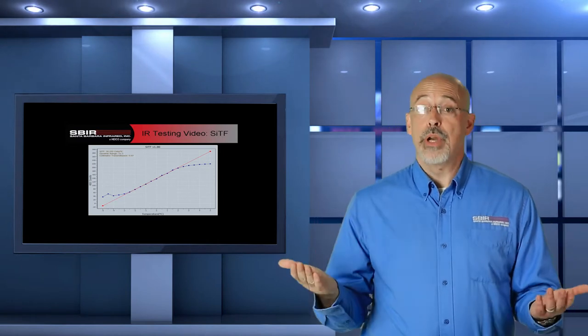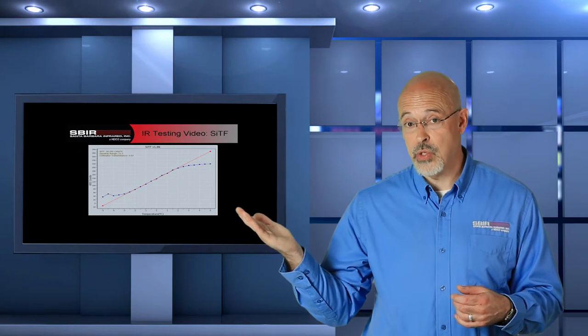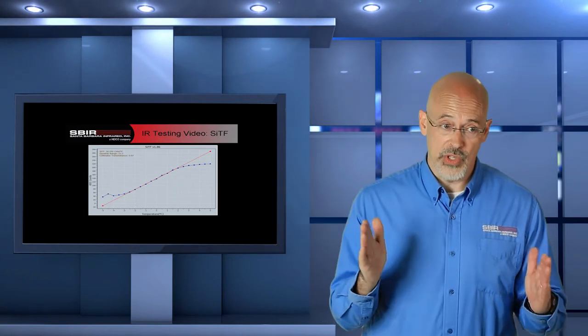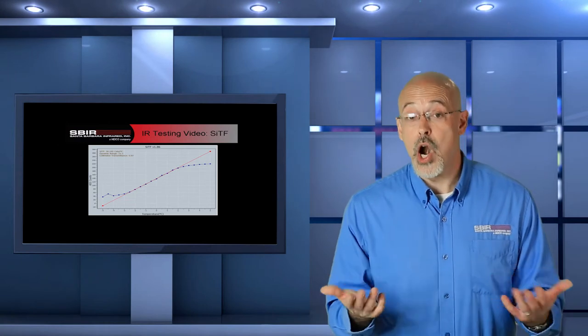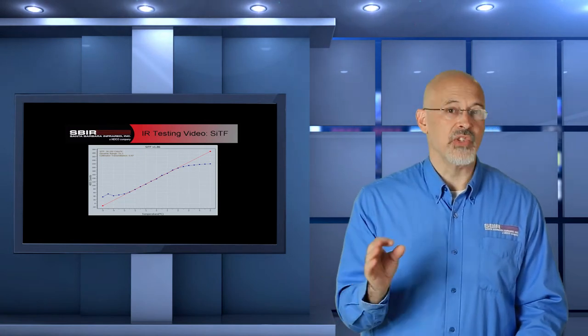That important middle region is where we take our measurement and look at the slope to calculate our SITF. We can also use the measurement to look at the operating range of the camera — we know when it doesn't get enough temperature to stimulate it, when it starts responding, and where it starts to saturate. That region of interest is our operating temperature range. We can also calculate dynamic range, which requires the noise measurement — we'll cover dynamic range in the next video.